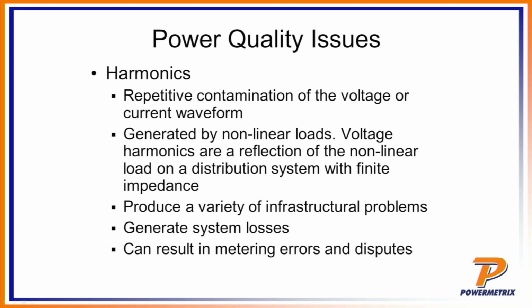Harmonics can cause a variety of infrastructural problems. In particular, it can generate system losses, and it can also generate excessive heat in the equipment. Transformers in particular don't like harmonics. Most distribution transformers were designed, of course, to transmit 60 hertz loads, and so if we start to have higher and higher frequency harmonics, that's going to end up generating extra heat in those transformer coils. Once again, most electronics don't like to run hot. It will reduce the overall lifetime of the equipment, and so you may have to replace equipment more often because of that. Harmonics can also result in metering errors, in particular VA and VAR error measurements. There's not a standard right now for those, and so depending on how that is being calculated, it can potentially cause some issues.